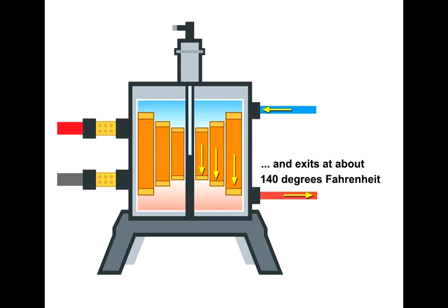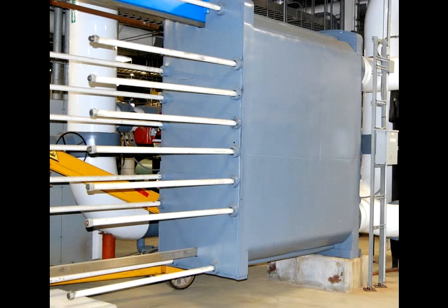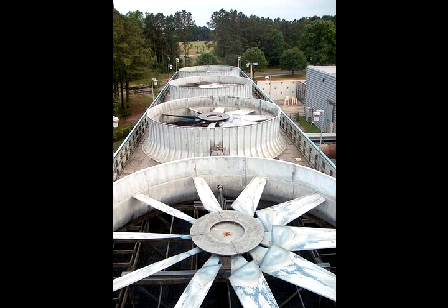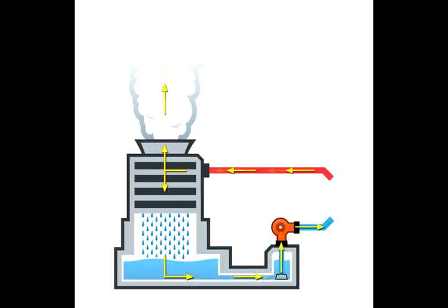That is a lot of energy we have to get rid of. Now that water goes out into the plant and goes to a heat exchanger where it gives that energy up, that thermal energy, over to the chilled water system. Chillers remove the heat from the chilled water system and move it over to our condenser water system which puts it out into the cooling tower. And the cooling tower cools the water by evaporation. We do our part to make Florida hotter and more humid.